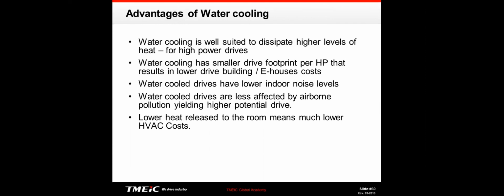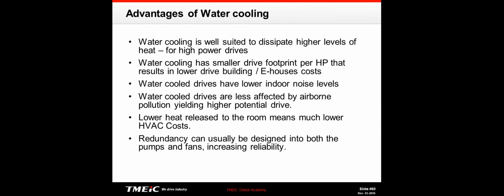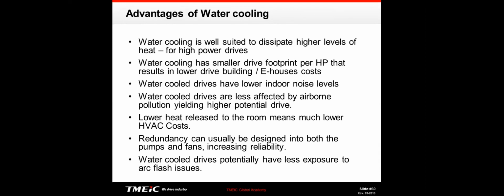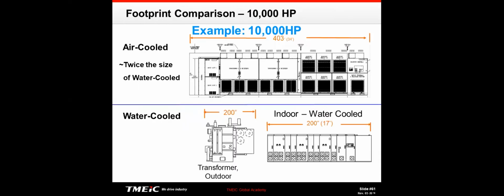And because water-cooled reduces heat into the room, you need less air conditioning in the room. And you can provide redundancy in pumps and fans and so on. Turns out water-cooled drives are actually even more reliable than air-cooled drives. And I showed you that one water-cooled drive that was a 28-year mean time between failure.